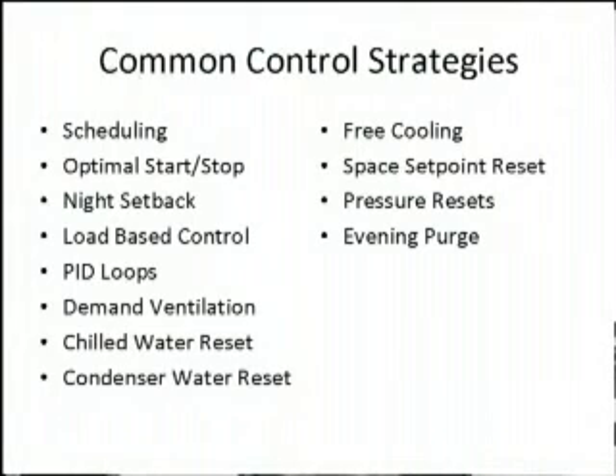Load-based control is kind of looking at your site instead of assuming you've got a certain load going on in there. Look at your terminal units to see what's going on, and it goes along with resetting of the other parameters that are going into the cooling process. Demand ventilation we talked about. Chilled water reset, that's again the same. It's trying to take advantage of savings when there is an opportunity without degrading your building. Condenser water reset, we're going to talk about later.